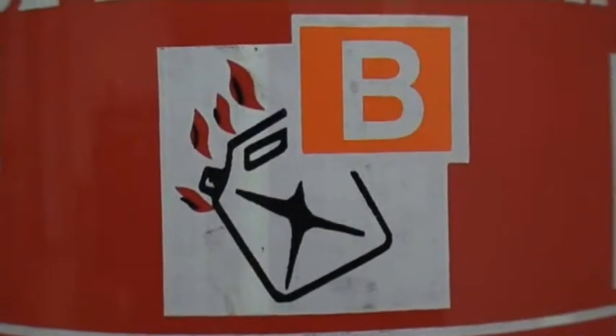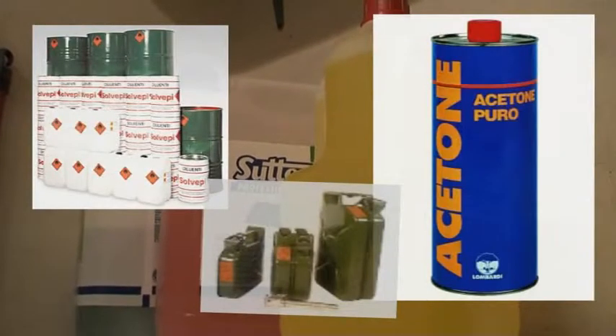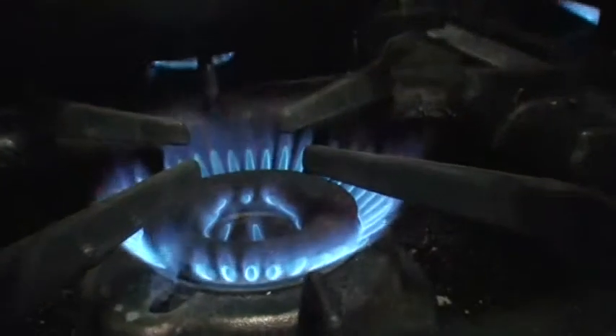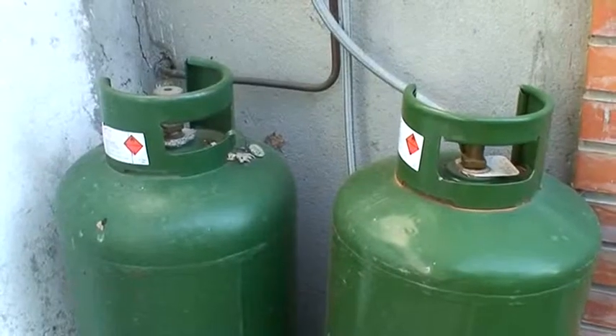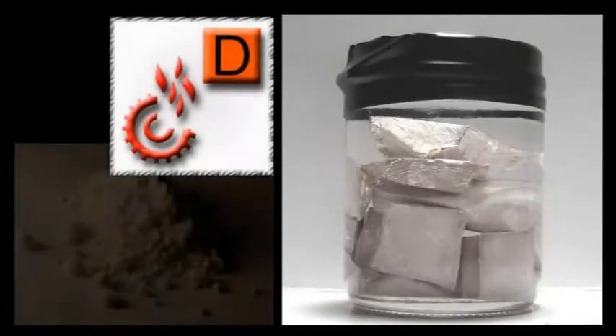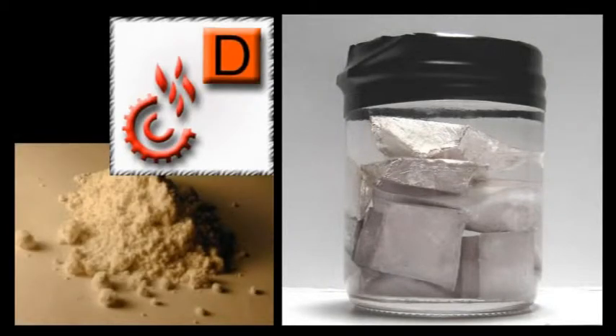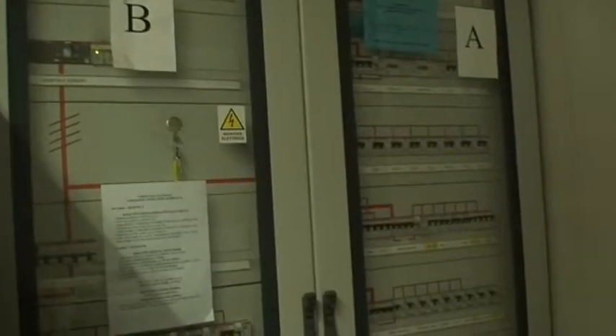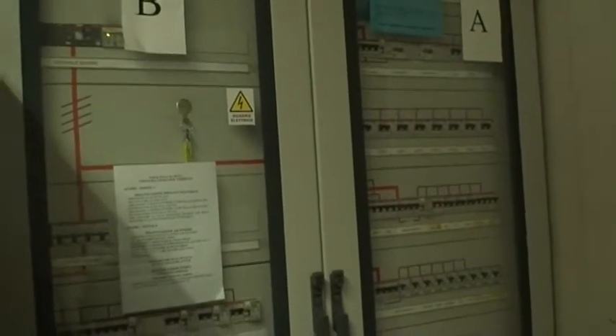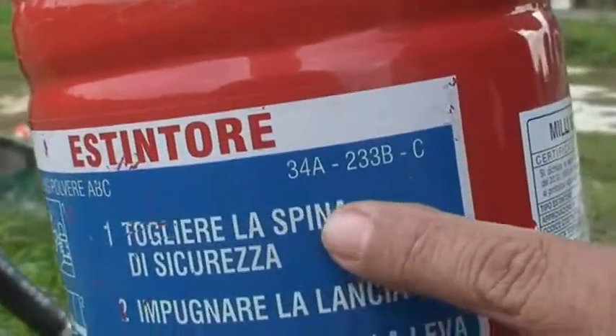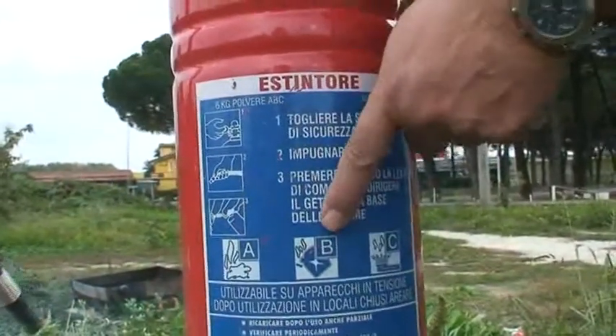Class B fires are those deriving from liquid combustibles such as petrol or gasoline, alcohol and solvents. Class C fires are those deriving from gas combustibles like methane, LPG, hydrogen and acetylene. Class D includes combustible metals such as magnesium, aluminium, sodium and potassium. Fires of electric origin are placed in a different class. A label on each fire extinguisher indicates its content, its potential and which class of fires it can be used for.